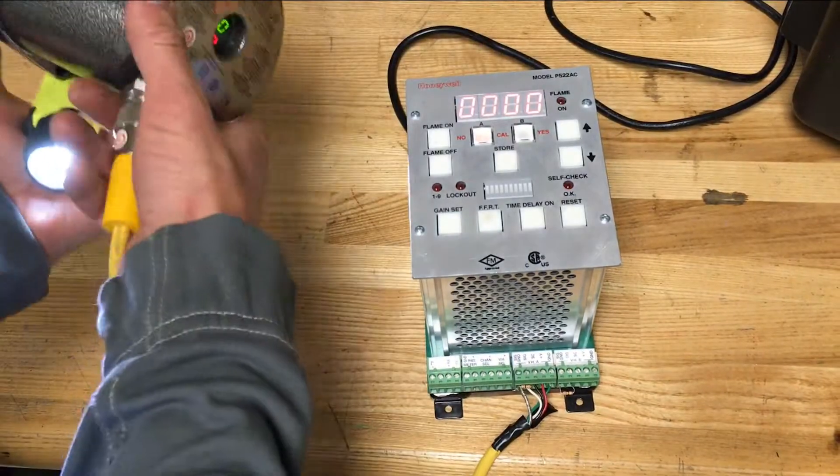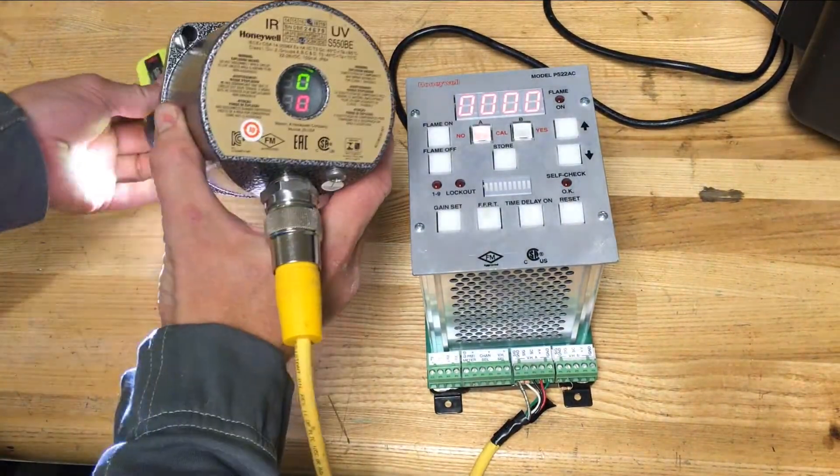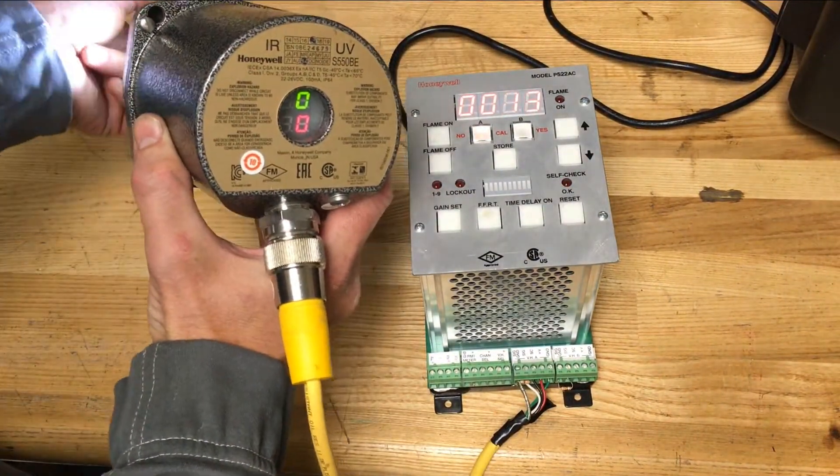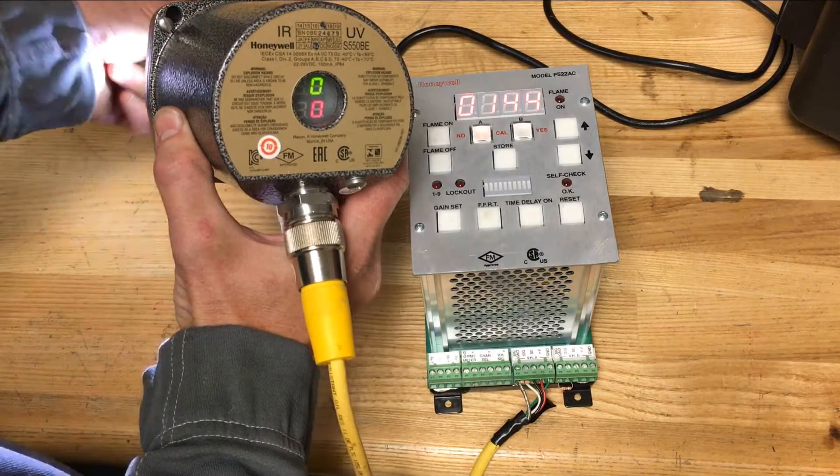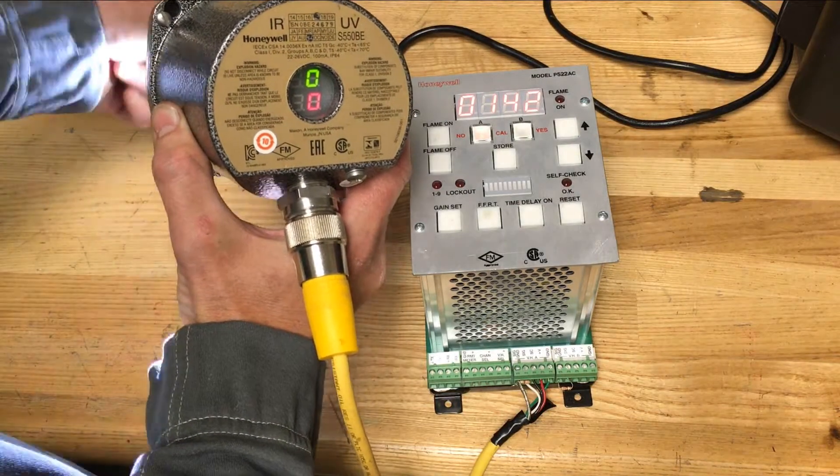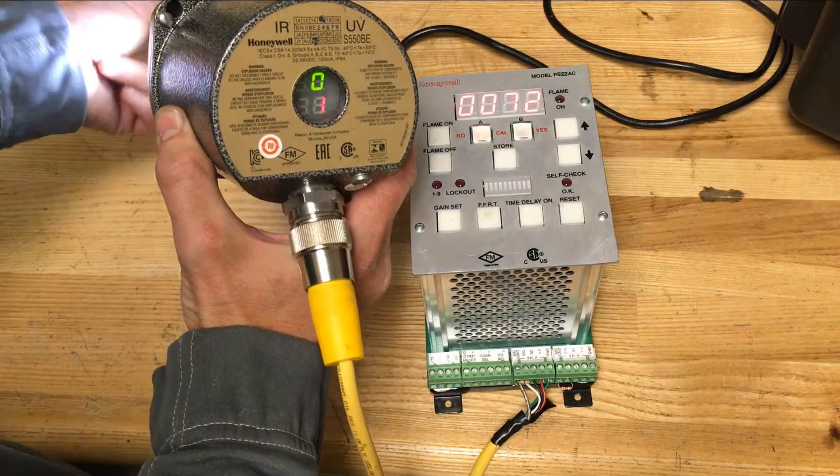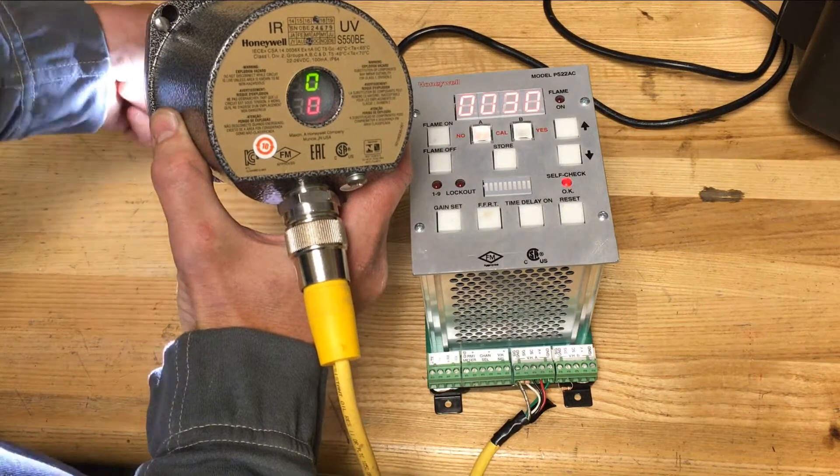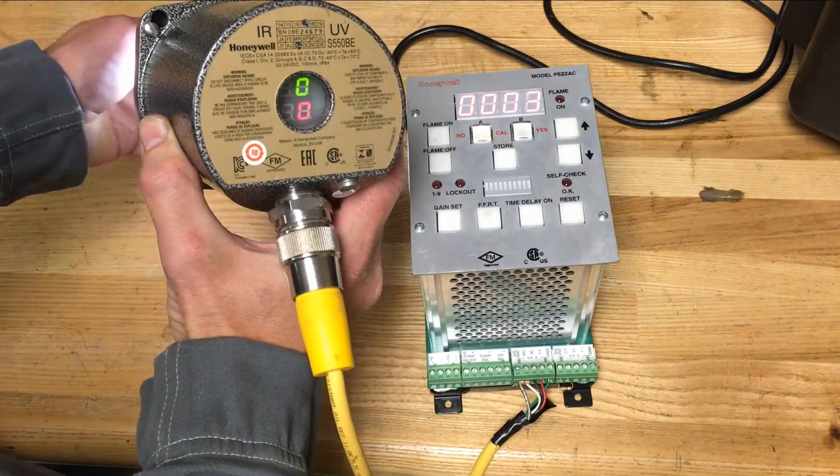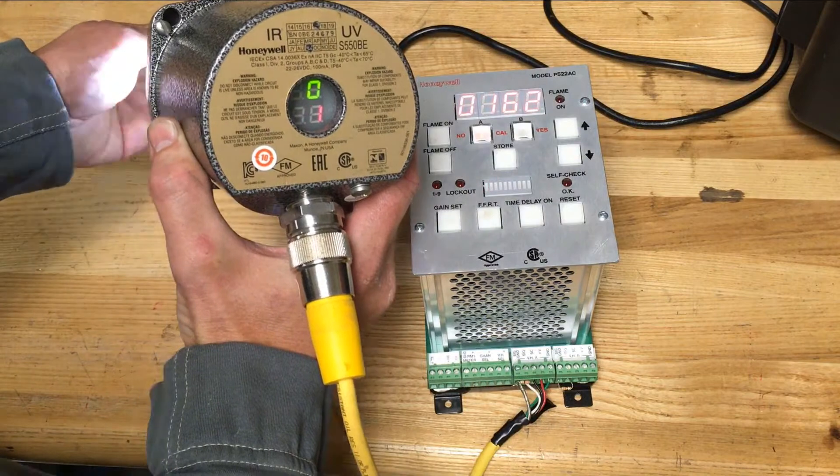The combo head has two different sensors. The IR sensor can be triggered by a standard flashlight and will be indicated by the red LED value on the viewing head. You must flash the light rapidly to get the head to trigger because it has frequency filtering.